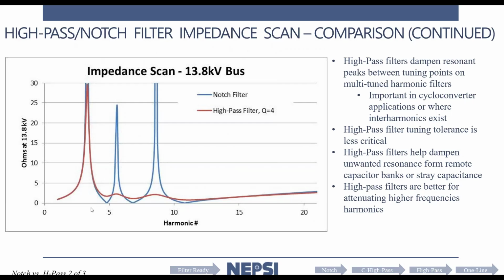So the red diagram represents the high pass harmonic filter system. The blue impedance scan represents a notch filter system. So here you can see that for notch filters we have these peaks, these blue peaks here, and they represent actual resonant points caused by the next tuned filter up. So if you have interharmonics, and that's what you see here, if you have an interharmonic, say here at the 6th, it would result in a high distortion. So installing a damped filter, a high pass filter, or a C high pass filter will help to eliminate these resonant peaks that exist between tuning points in a harmonic filter system.